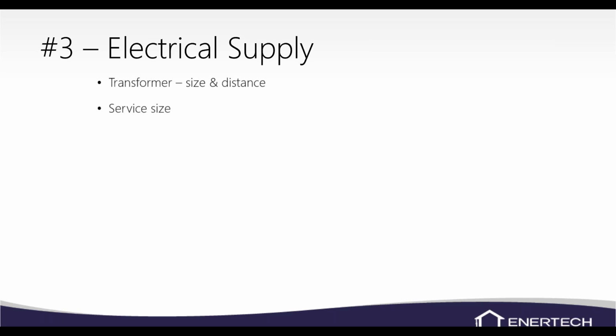Make sure they've got proper service size, panel size. If you're installing a geothermal unit with electric backup heat, you're going to have 2 power sources to the unit. It could be like an 80 amp breaker for the electric heat and probably a 50 or 60 for the geothermal unit. So you've got to make sure they have enough access in their service panel.